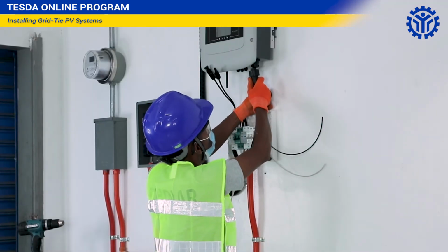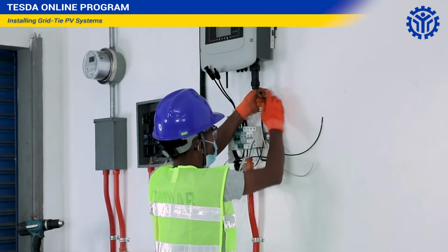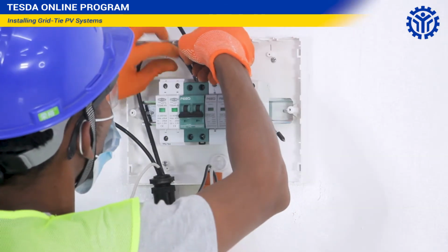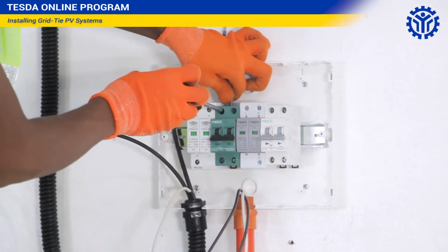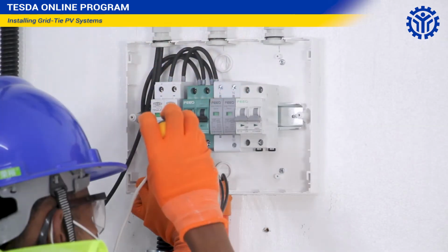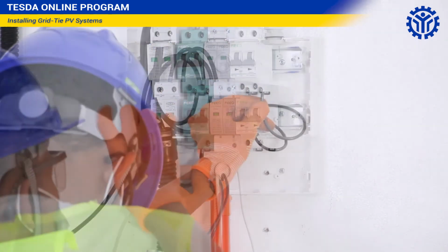Wire the inverter according to the diagram. Secure all the wires and connections of the AC circuit breaker, DC circuit breakers, SPD, grounding bus bar, and CT sensor.